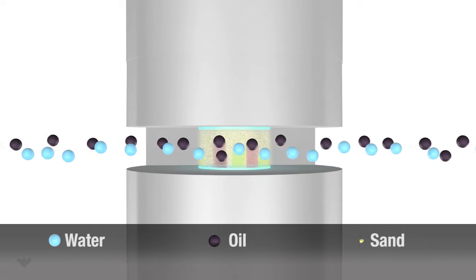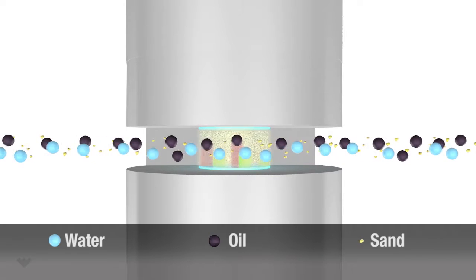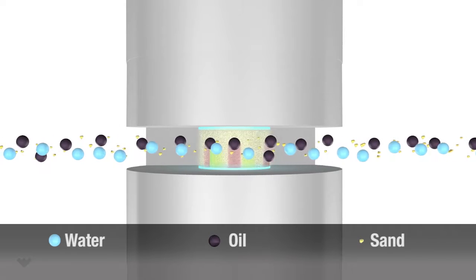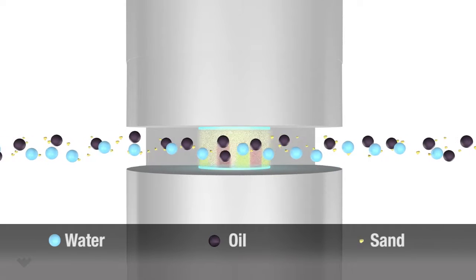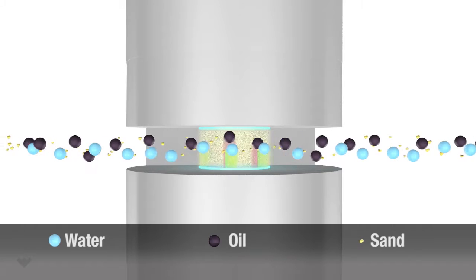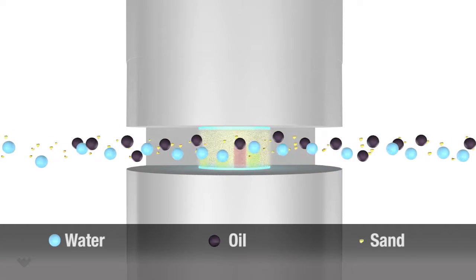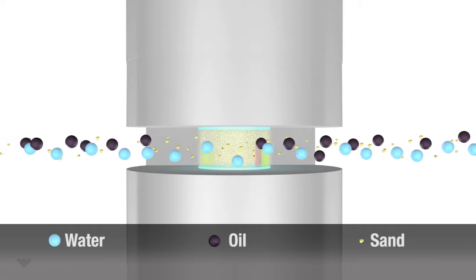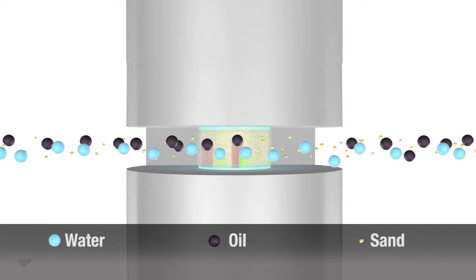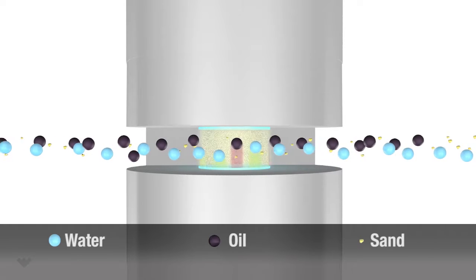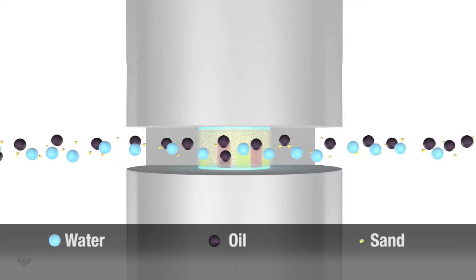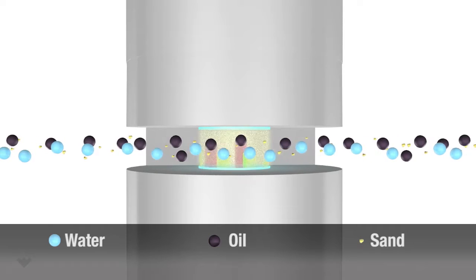The Red Eye water cut meter is also effective in wells with emulsions and sand, which cause scattering of the optical signal. However, because the effect is equal at all wavelengths, the meter simply nulls the scattering effect with no impact on water cut measurement.